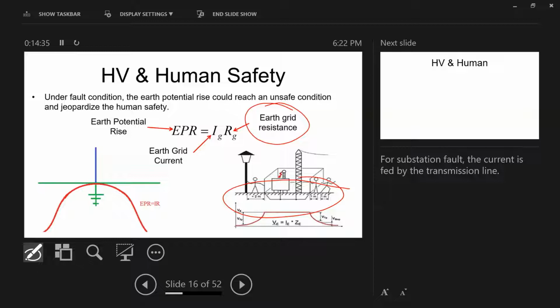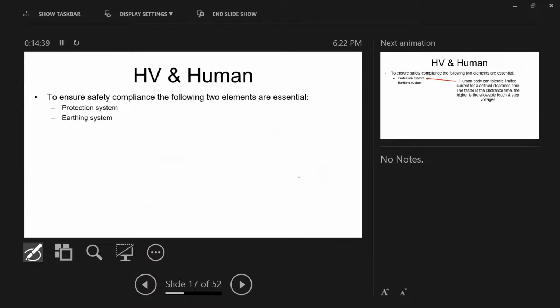You will see now what will happen. Now, to ensure our human body is protected, they've done a lot of study. Our body can withstand voltage for a small period of time. For example, the clearance time, the time to isolate the fault: the smaller it is, the higher the voltage I can tolerate. So this is very critical.